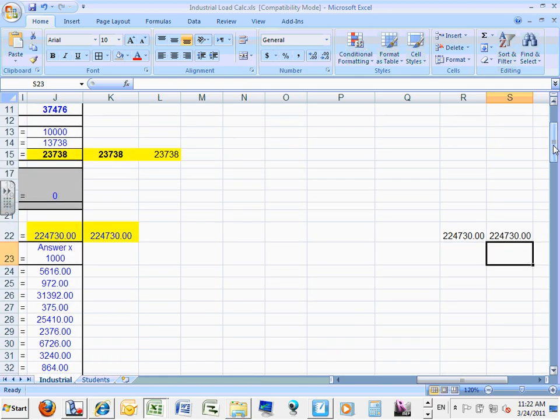See how easy that is, guys? You know how this particular one goes? Here's the PDU, fed from the UPS, and the UPS fed from the switchgear, right? So if I have the load here, it's going to be seen by the PDU. The same load will be seen by the UPS. The same load will be seen by the switchgear. The PDU is a special animal. I agree with you, we should have done the riser.